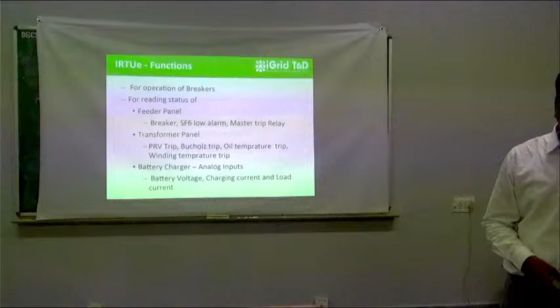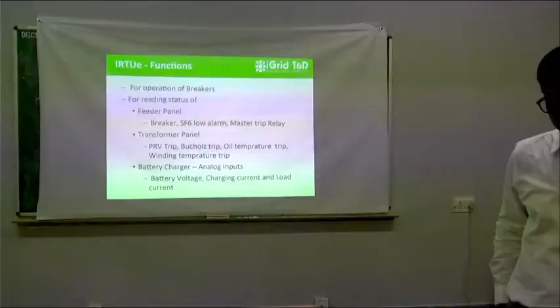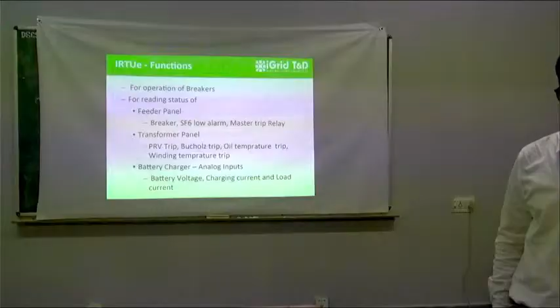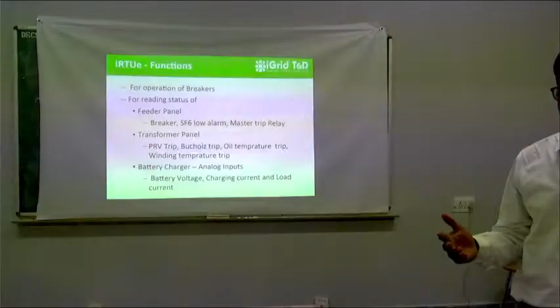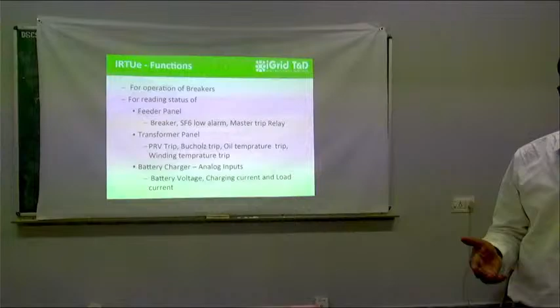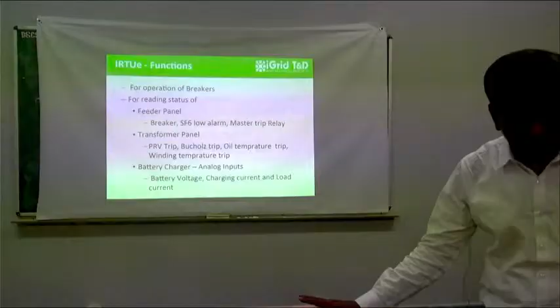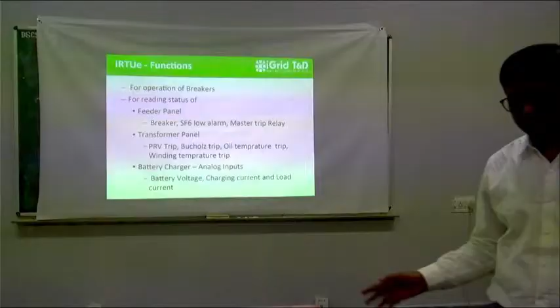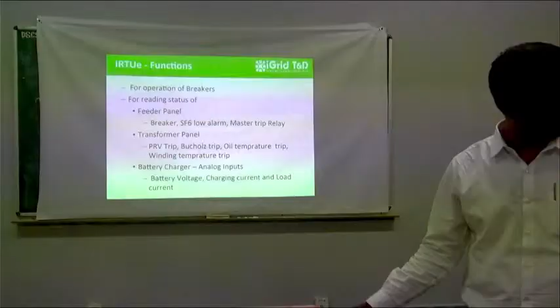We call this RTU an IRTUE because it is nothing but an extension unit. So we use IRTUEs for the operation of the breakers, and also, as I told you, for reading the status of the feeder panel. Say I want to get the status of my breaker, the SF6 gas low alarm of my breakers, the Master trip relay status. If it is a transformer panel, I will get Buchholz trip, oil temperature trip, winding trip. All these things are connected to the digital inputs of my RTU. In addition, I want to see the status of my battery, and you have transducers which give me the data, connected to my analog inputs.